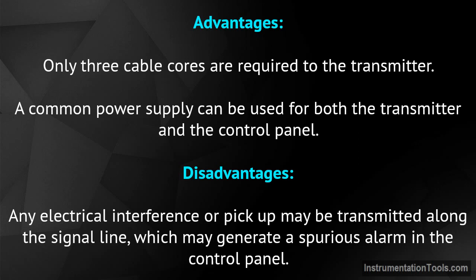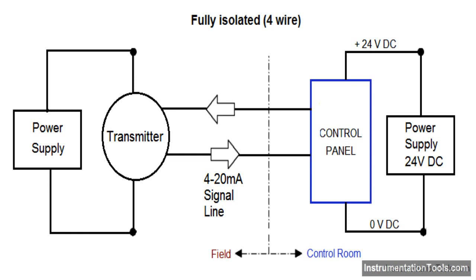A common power supply can be used for both the transmitter and the control panel. Disadvantages: any electrical interference or pickup may be transmitted along the signal line, which may generate a spurious alarm in the control panel.